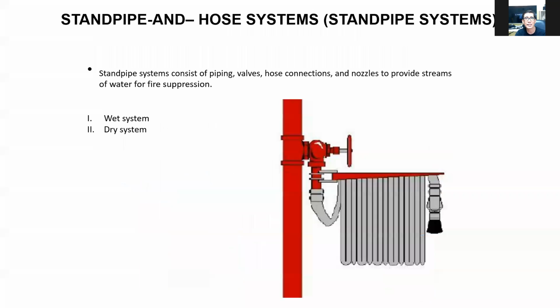And we have the standpipe and hose. Okay, so this is what you usually see in buildings, no, the standpipe and hose. This is usually inside a cabinet, and this cabinet contains the hose and the standpipes, no. And this can be either dry or wet. Okay, if it's wet, it means that this pipe is filled with water. If it's dry, this pipe has no water. And you need to connect the hose from the fire truck to a Siamese connection so that both pipes will be filled with water. So we have two types of standpipe system, the wet type or the dry system.